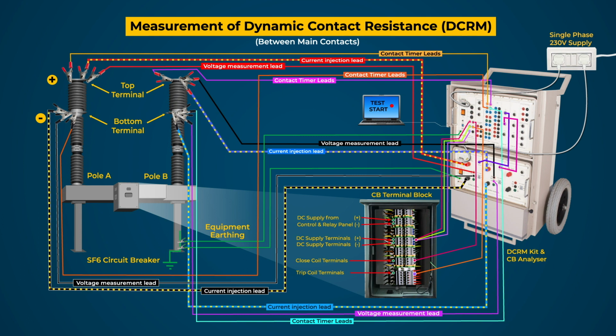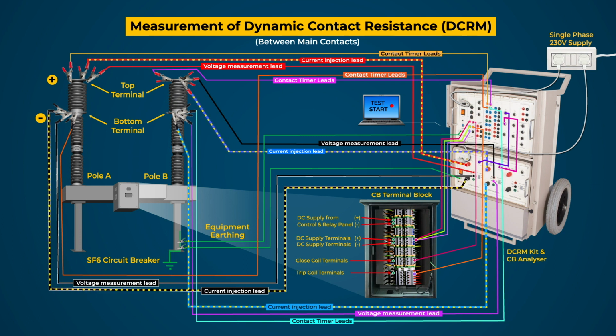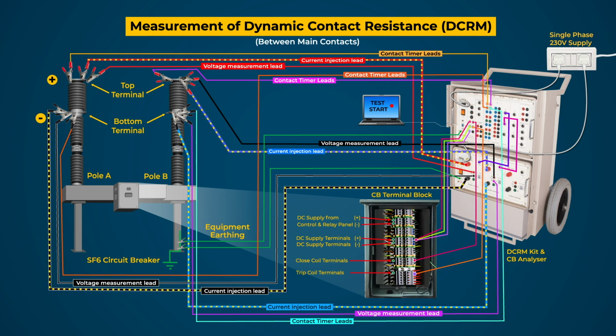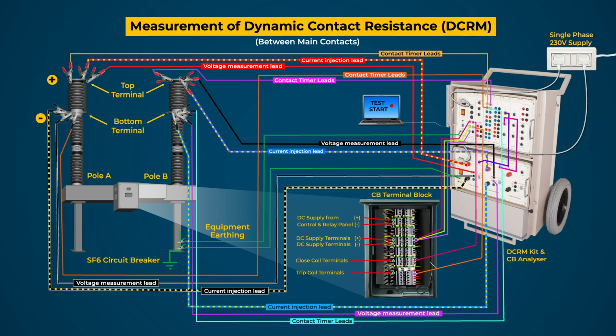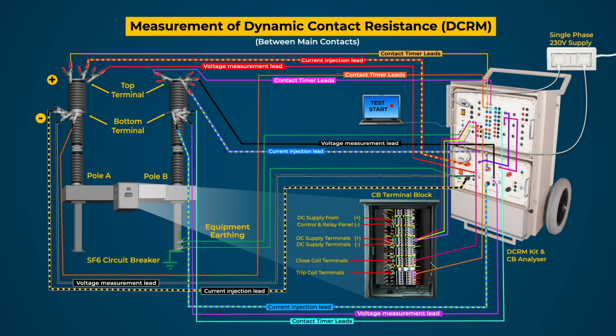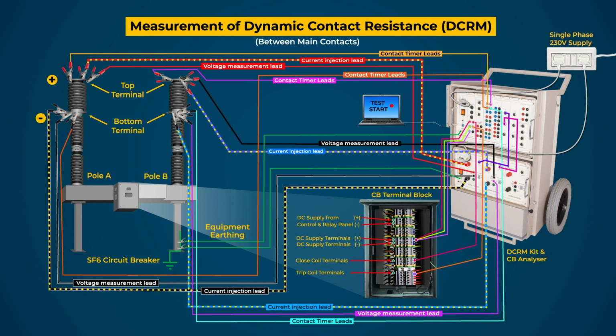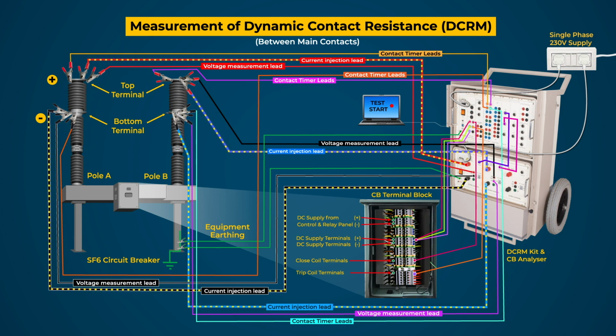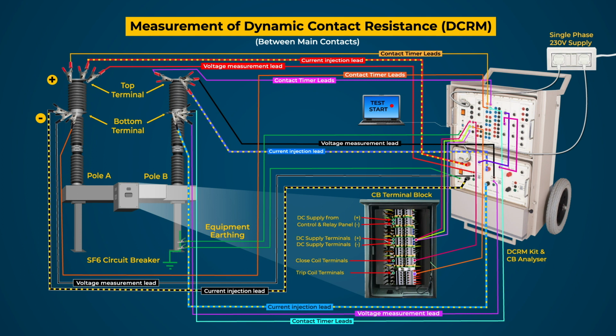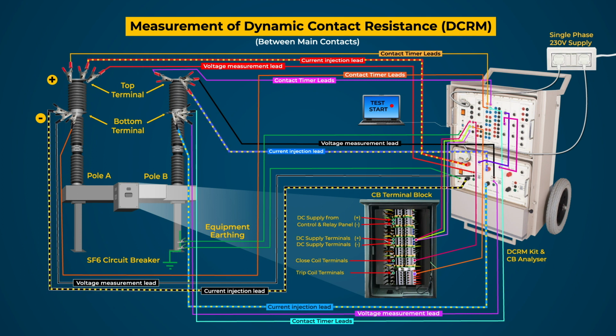These data are measured by the DCRM kit and sent to the CB analyzer kit, where the analyzer monitors the contact resistance over the time of operation. The CB analyzer plots the contact resistance over the operation time, which gives the realistic variation of contact resistance.